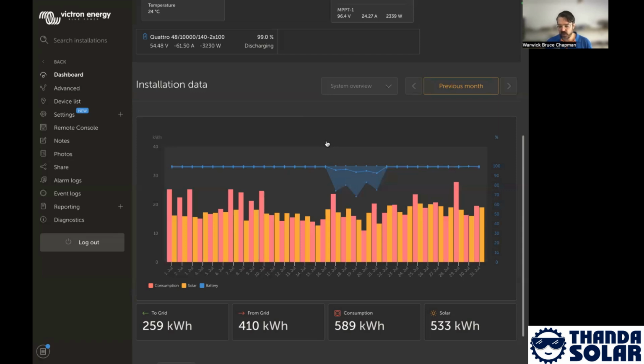startup loads like motors, where the motor is rated as a 10 kilowatts, but it requires 40 kilowatts to get started. Can the inverter provide that instantaneous peak power just to get that motor started before it settles down to its 10 kilowatts? And so the conventional wisdom has always been, and certainly our experience in the field, is that the transformer-based old school stuff can be relied upon for that. But from what we've seen from the multi-RS family and the very early testing of the HS family, they seem to stack up. They seem to be delivering comparable performance with improved efficiency and with improved output power quality. So we're very excited about those.